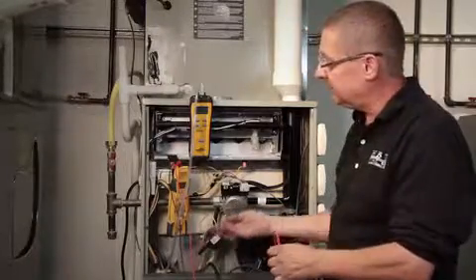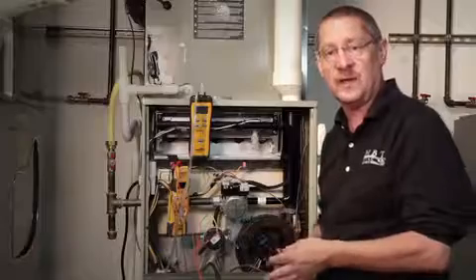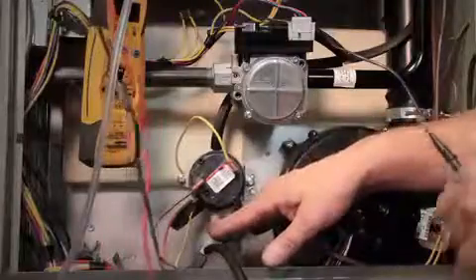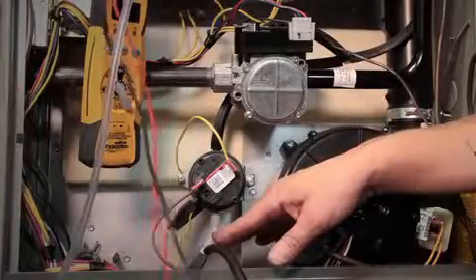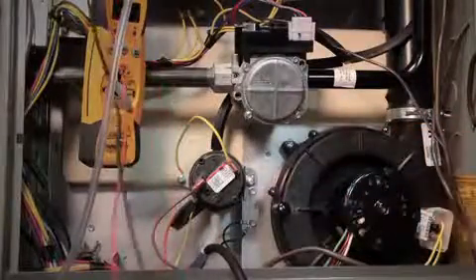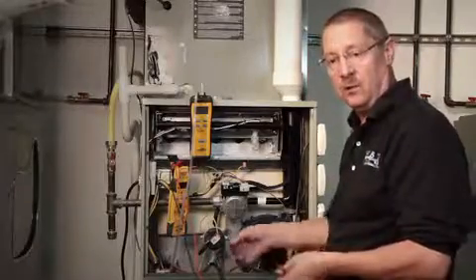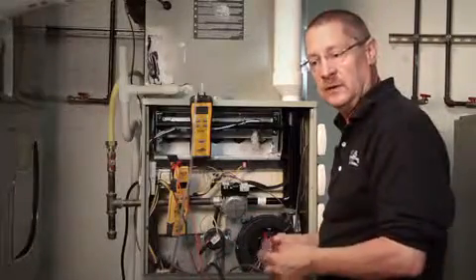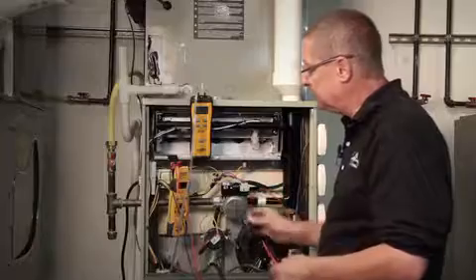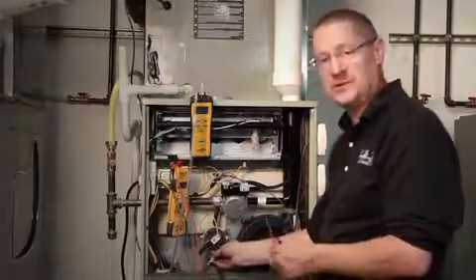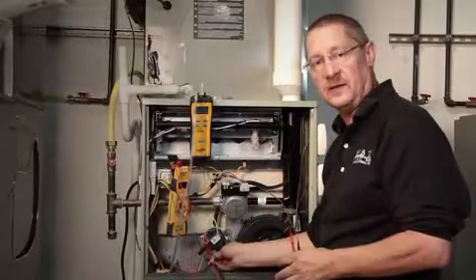If I did not get deep enough vacuum, we've got to ask ourselves why. So we tee into this so we can measure. Make sure that vent hose is not plugged up. We're going to check the connection at the firewall or where it plugs into the venter motor assembly. Make sure that's clean and clear, that this can actually sense what's going on inside that heat exchanger.